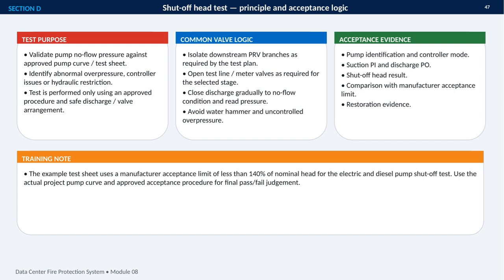The acceptance record should identify the pump and controller mode, document suction and discharge gauge readings, capture the shutoff head, compare it with the manufacturer's acceptance limit, and provide evidence that the system was restored afterward. As a training example, the test sheet uses a limit of less than 140% of nominal head for both electric and diesel pumps. Final pass or fail decisions must use the actual project pump curve and approved procedure.